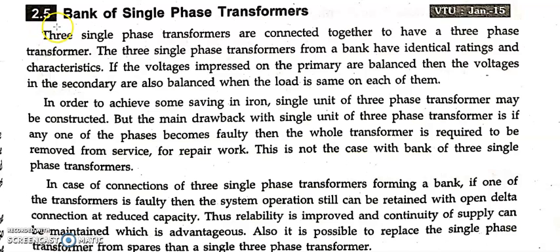The last class we were discussing about bank of single phase transformers, wherein we came across the major drawback of using single three phase transformers, that is, if one phase becomes faulty, then we have to change the whole transformer. That is, we have to remove that particular transformer from the service for the repair work. So this doesn't happen with respect to using bank of three single phase transformers.